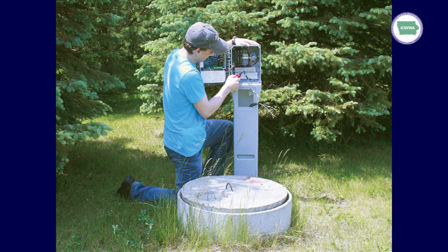I've actually seen panel installations where if you want to do service work on it, you got to lay on the ground because the panel is about 1 foot off the ground. So to do any wiring to it or do any service on it, you got to lay down. It just doesn't make any sense to me. I certainly understand why it sometimes gets done that way. People try to minimize the impact of a panel being out in somebody's backyard, and so they may keep the installation low. You got to think about the service down the road.